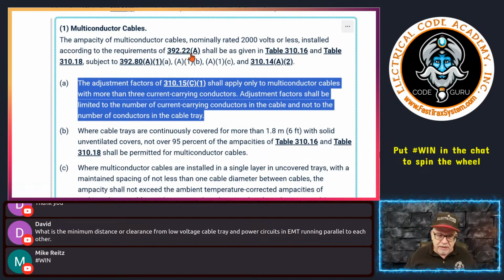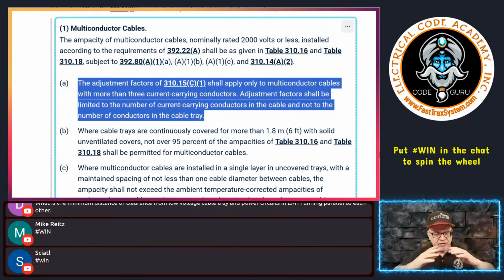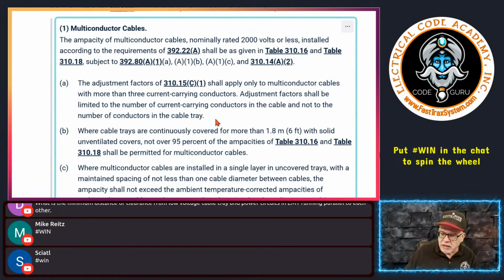So these are going to help limit it anyway, because it's going to say whether it needs to be 1 layer. This is going to say whether or not there's a certain amount of fill that can be in there. So all that plays together, okay? So don't freak out about it. But what's really important in this scenario is that it does not negate the fact that you may have to make an ambient temperature correction, okay? That still may be in place.